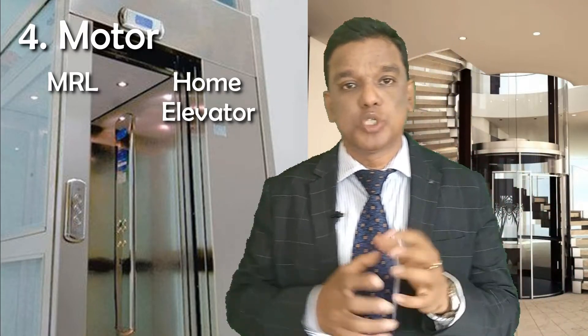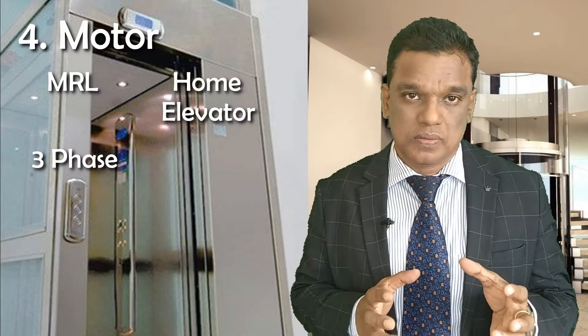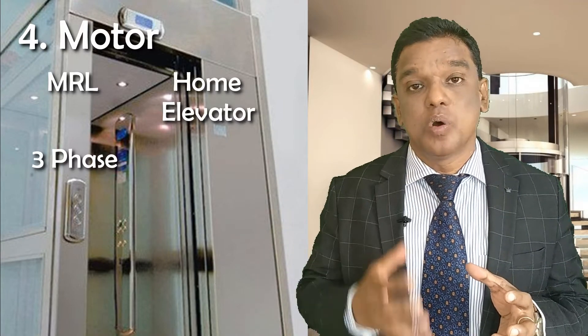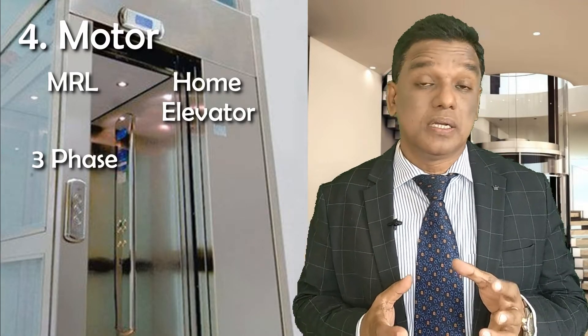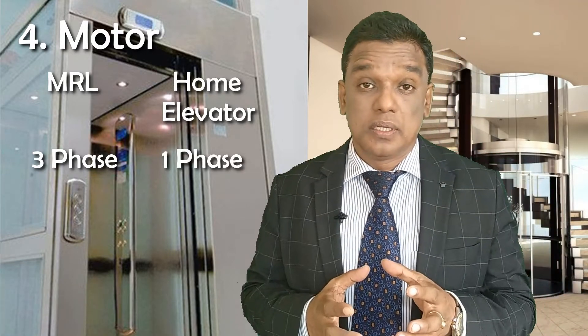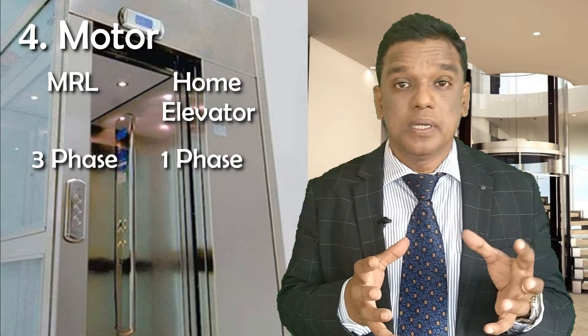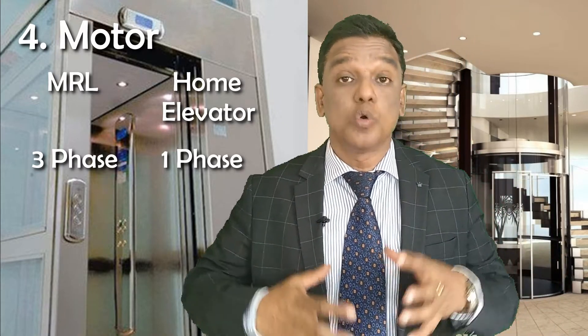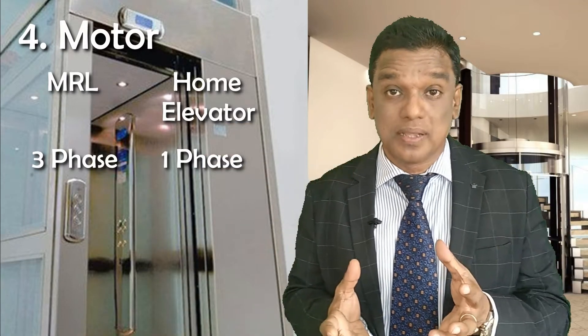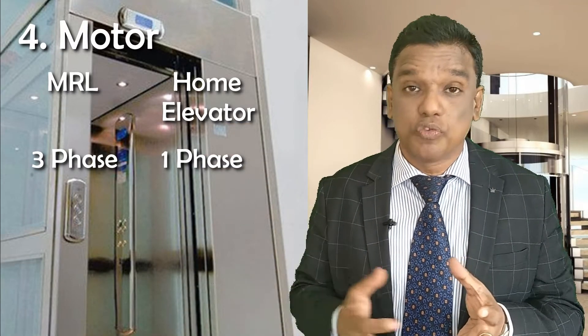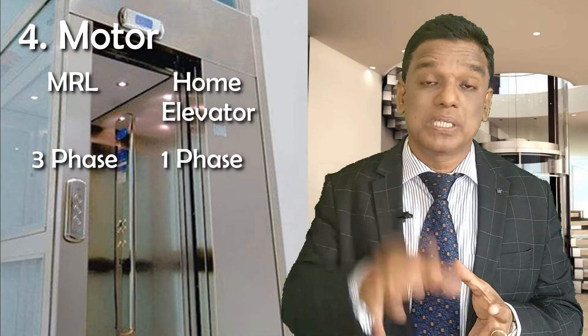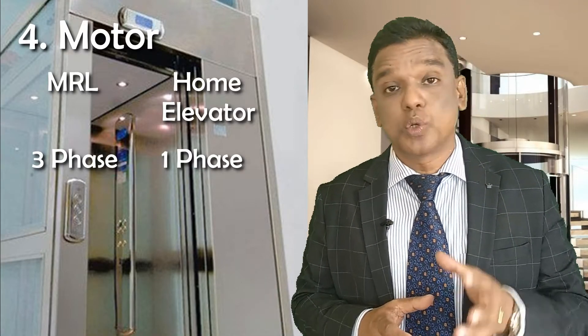Point number four is the motor. In MRL — machine room less elevator — the motor used is a three-phase motor, so the customer has to provide three-phase power supply. At the same time, in a home elevator the motor is a single-phase motor. A home elevator is typically installed where the customer does not have three-phase power supply or where three-phase supply is not available in the area. In that case, a single-phase motor is used and a home elevator is the best option compared to MRL.